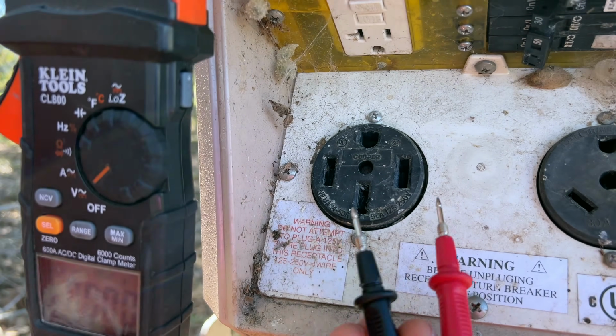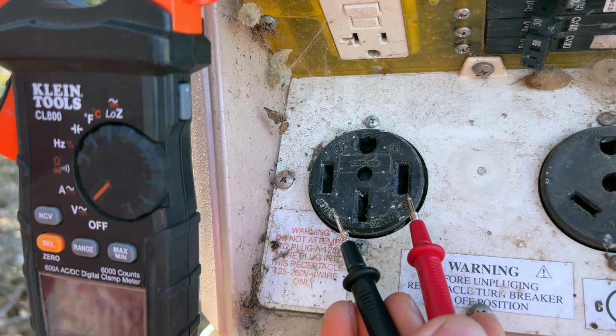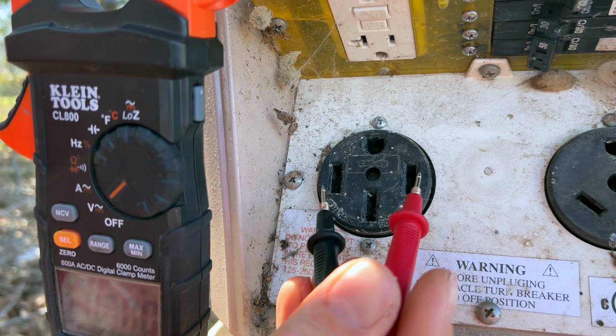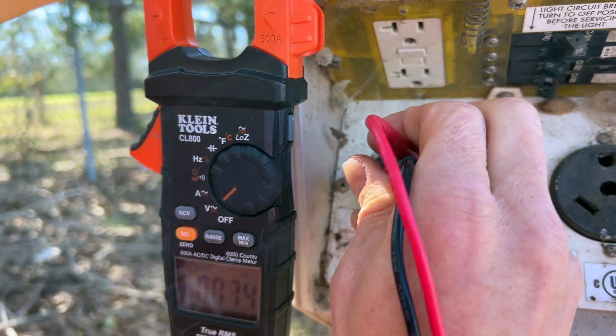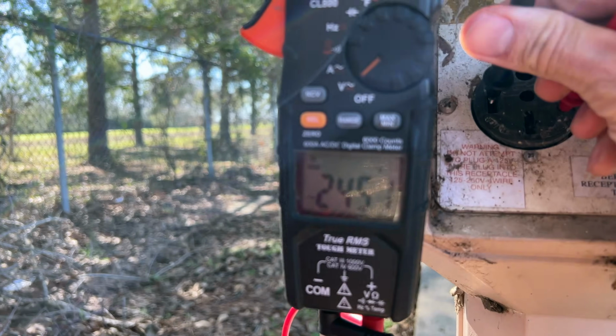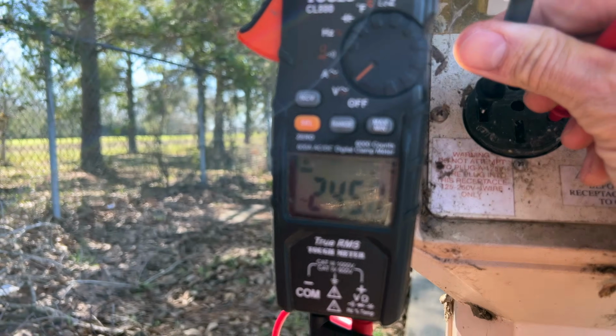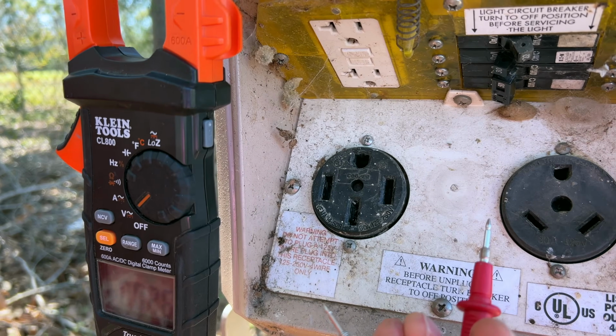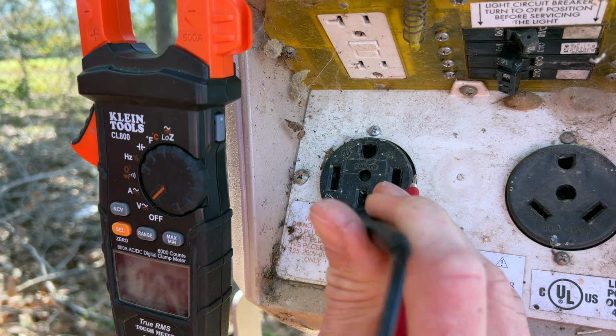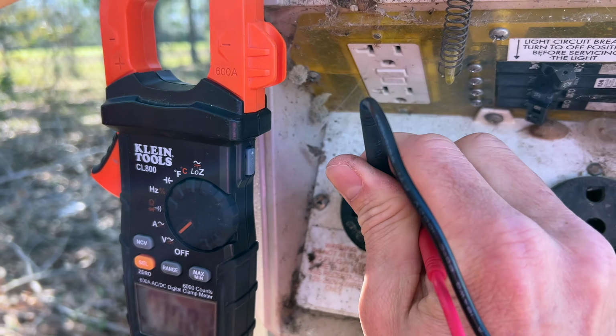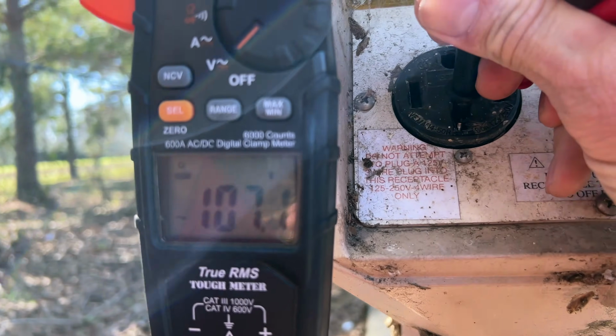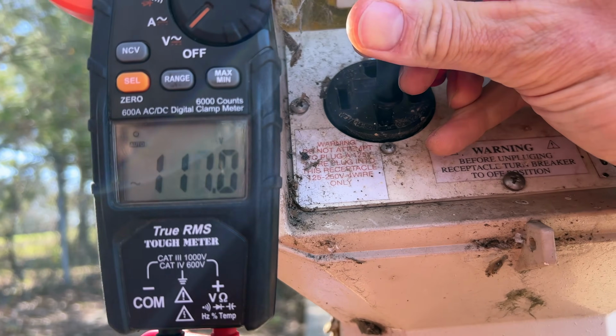So I'm going to take my red lead, put it into my right hot leg, my black lead into my left hot leg. Doing this, I should read around 240 volts. So that is good. Now I'll put my red lead into my hot lead on the right and my black lead into neutral on the bottom. And you should see 120 volts.